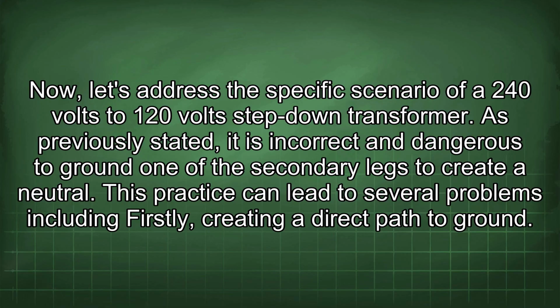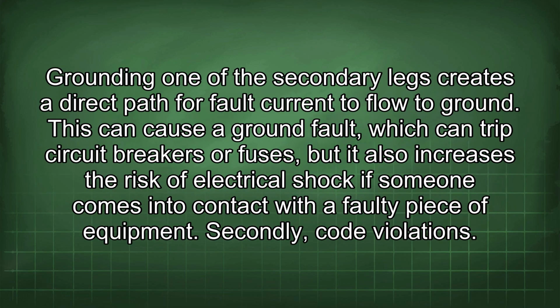As previously stated, it is incorrect and dangerous to ground one of the secondary legs to create a neutral. This practice can lead to several problems, including, firstly, creating a direct path to ground. Grounding one of the secondary legs creates a direct path for fault current to flow to ground. This can cause a ground fault, which can trip circuit breakers or fuses, but it also increases the risk of electrical shock if someone comes into contact with a faulty piece of equipment.